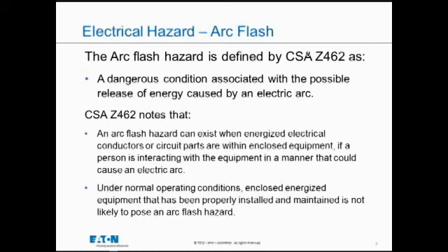It's a dangerous condition associated with a release of energy caused by an electric arc. Well, that release of energy can be light energy, heat energy, pressure wave, shrapnel, molten metal, toxic gas. There's a whole range of things that are nasty things that are coming out of an arc flash. What we're dealing with for analysis and PPE and labeling so far is just the heat hazard. We're not dealing with the pressure wave, other than we want you to wear ear protection for the pressure wave.